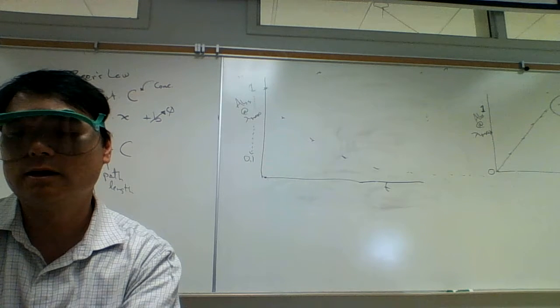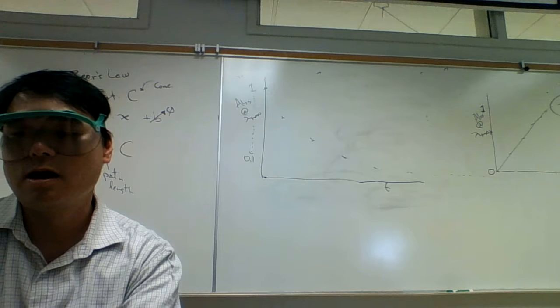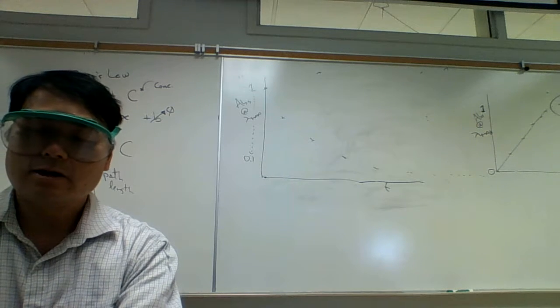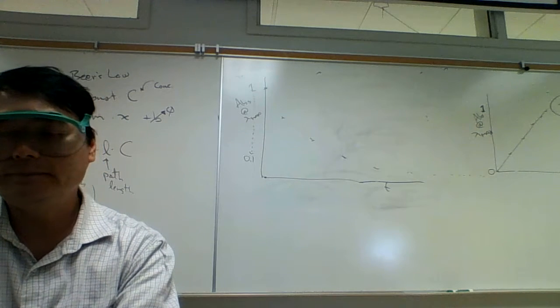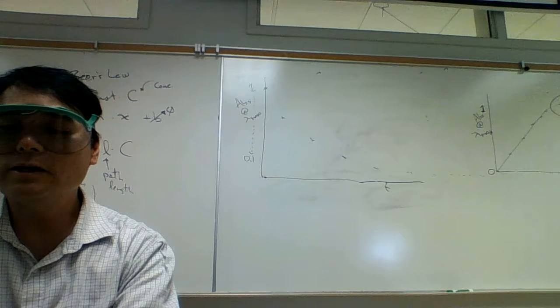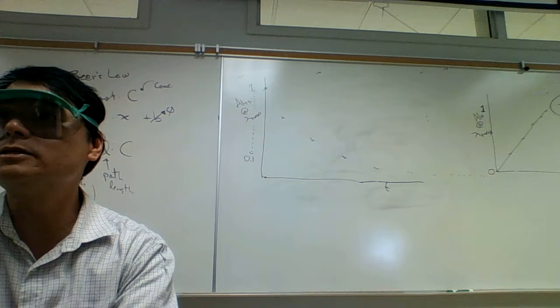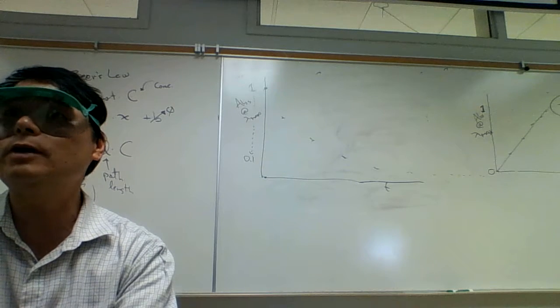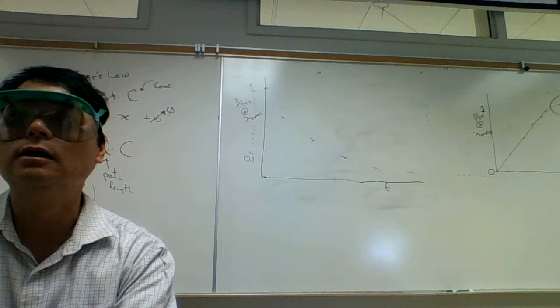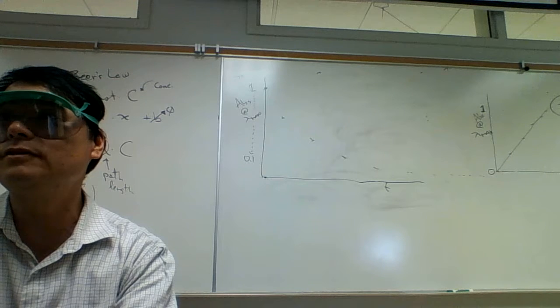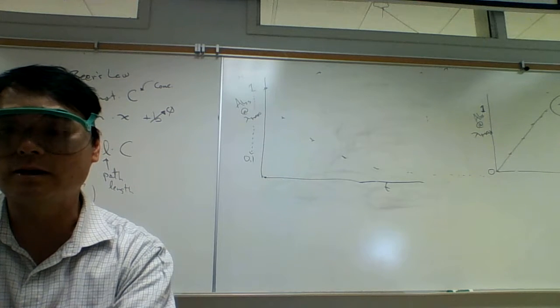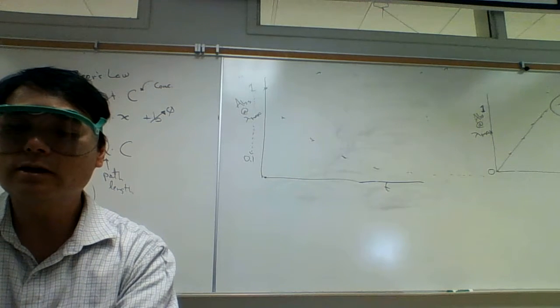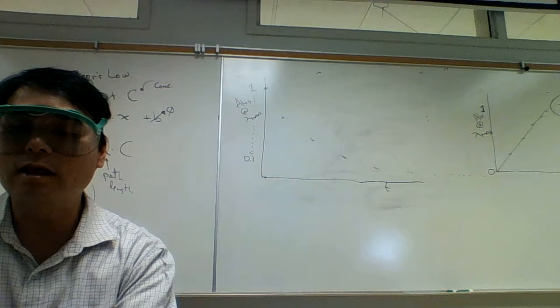Click OK. All right, I'm going to discard the previous data. We don't really need it. Now I want to calibrate this at the correct wavelength. What we did was a full spectrum calibration, but now that we have a specific wavelength we want, we're going to calibrate it at that specific wavelength to make sure it's properly calibrated. And so click on the red field and click Calibrate.